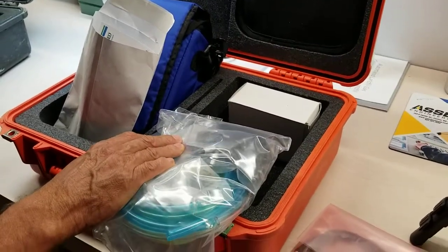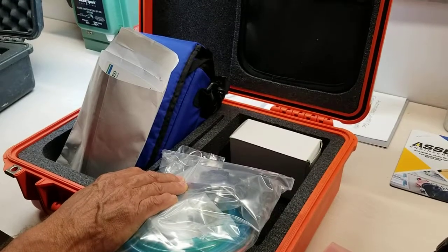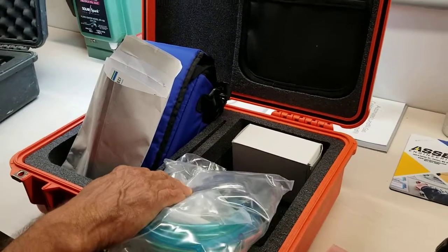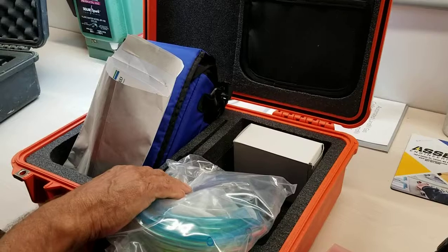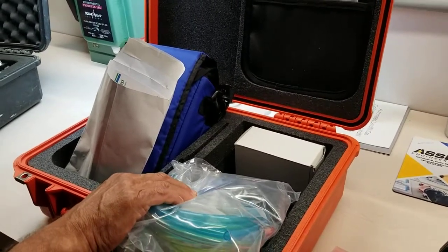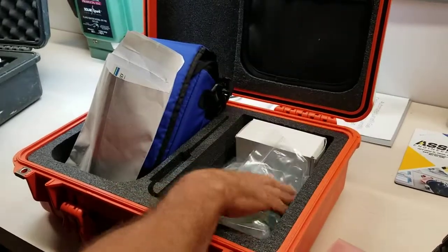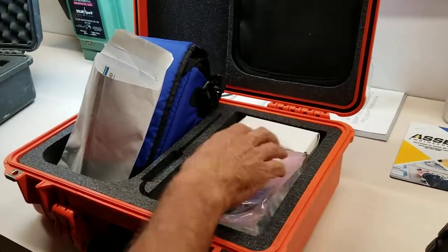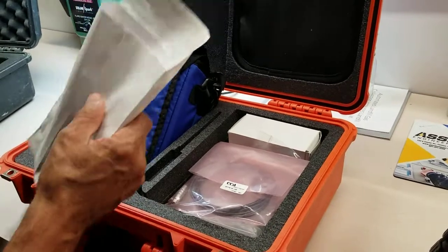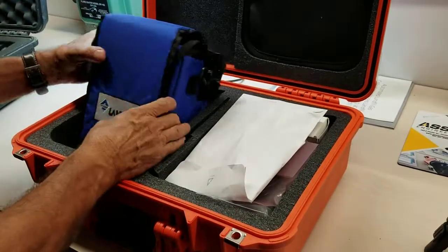Also included are a chrome mill quick disconnect — all part of this nice little package we sell with it, called the accessory package. It also includes the charger, the LandTec system gas analyzer software, and the USB download, so this unit is prepared for the technician to basically plug and play when he or she gets to the landfill site.